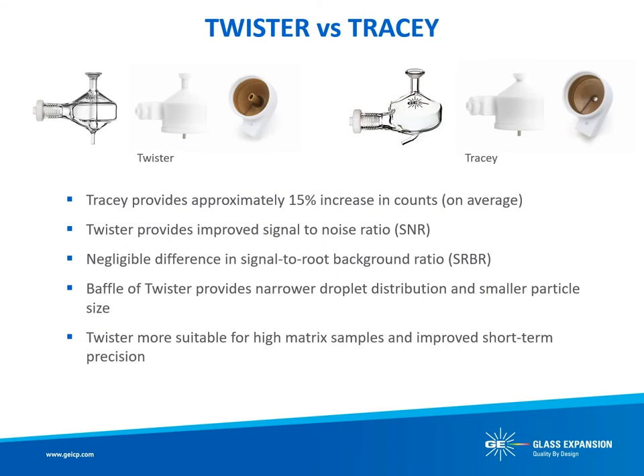The Twister cyclonic spray chamber features a central transfer tube, often referred to as a baffle or a double-pass cyclonic. This feature provides a smaller particle size and more narrow droplet distribution compared to our single-pass cyclonic, the Tracy. While the Tracy provides greater transport efficiency leading to greater sensitivity, greater sensitivity is not always the best solution. Smaller droplet sizes reduce matrix effects and improve short-term precision, making the Twister the most suitable choice for high-matrix samples, and the PTFE Twister most suitable for high-matrix samples containing hydrofluoric acid. The reduced sample load helps increase torch life, slow salt buildup at the injector tip, and decrease the frequency of cleaning ICP-MS interface cones.